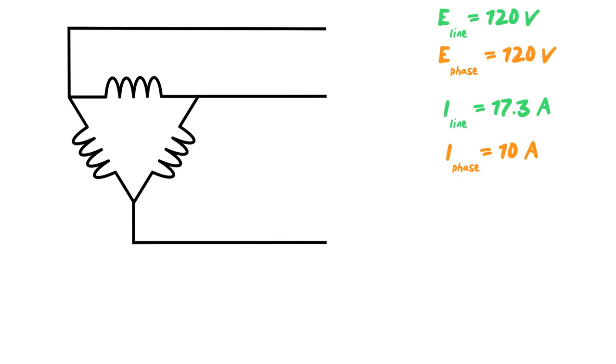So now what we can do is we can use those formulas that we talked about earlier in the video to see if they all come out to be fairly close to one another. So let's take VA equals 1.73 times E line times I line, E line 120 times 17.3 times root three will give us our answer. And there we go. We end up with roughly 3,600 VA. 1.73 times 120 times 17.3 gives us 3,591.8 VA. But for all intents and purposes, let's just kick it up to 3,600.